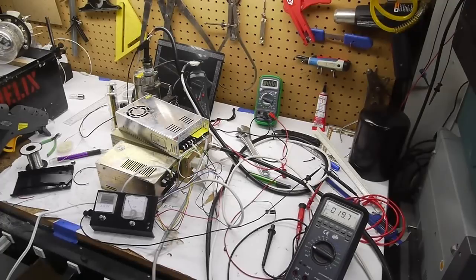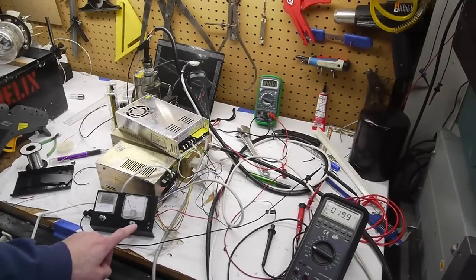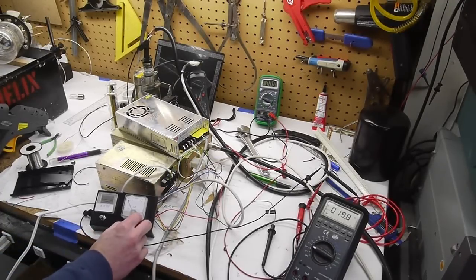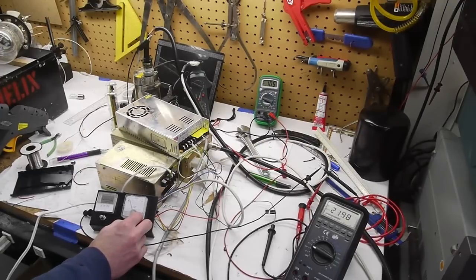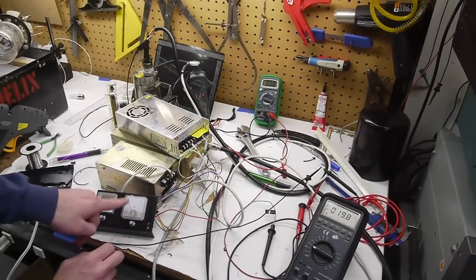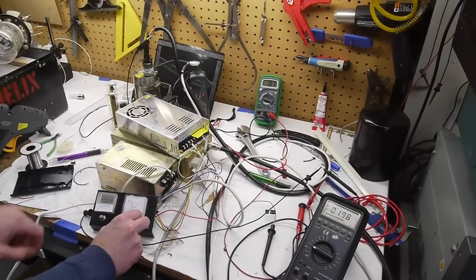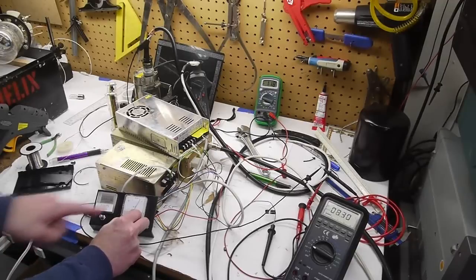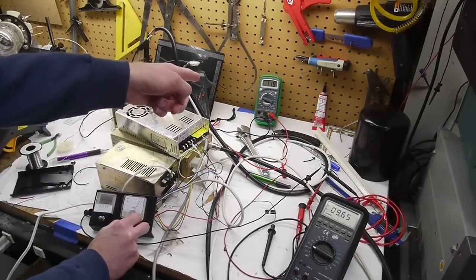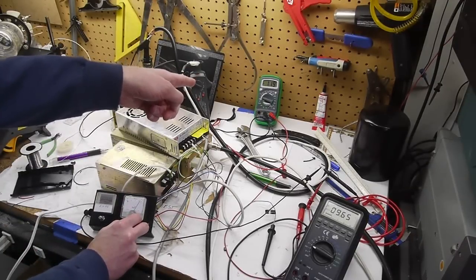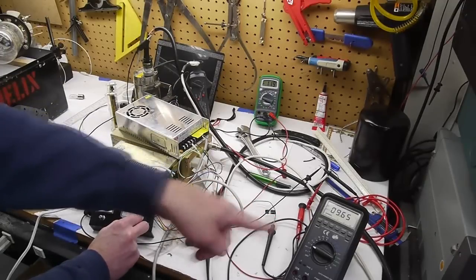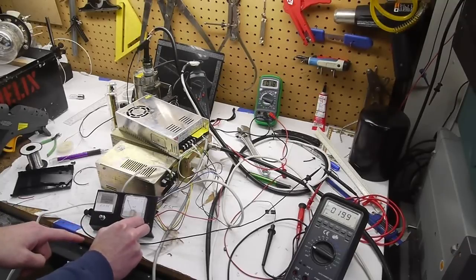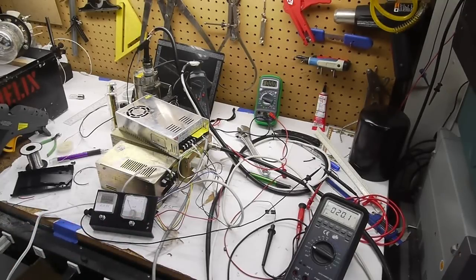And now I'm going to plug in the filament supply. Okay, and nothing's happening yet because I haven't set the current set point here. So if I turn this up a little bit, we can see there's activity and we're getting some readings here. And that was just a little burst. So if I turn this up almost all the way, we can get up to about 1 milliamp of emission. There's about a tenth of an amp flowing through the filament. And the current meter here is also agreeing with the 1 milliamp.